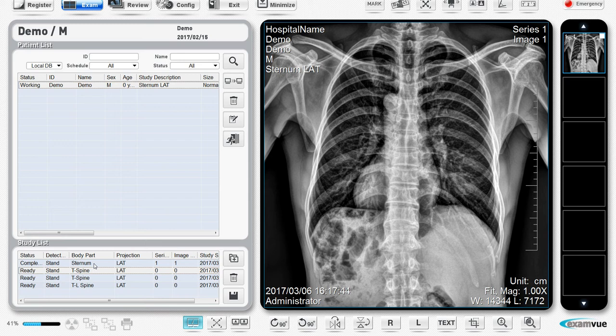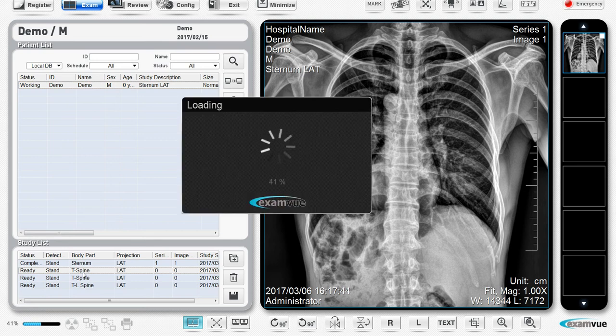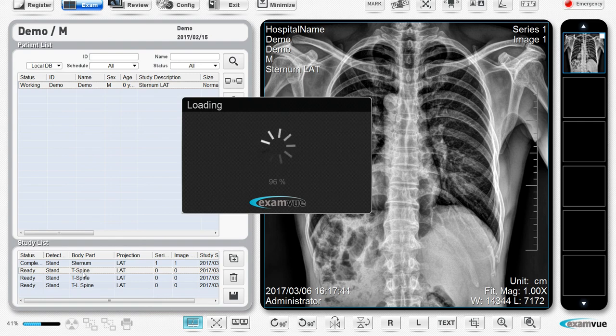If you want to retake an x-ray, simply select that shot and take a second exposure. It will add another shot to your exam. The old one won't be deleted and no x-rays can be deleted from Examvue during an exam, only rejected.